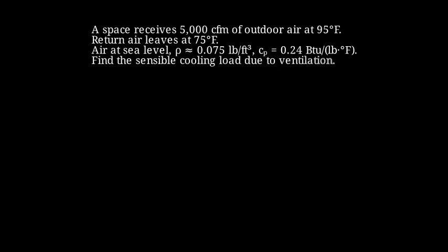Let's calculate the sensible cooling load due to ventilation. A space receives 5,000 cubic feet per minute of outdoor air at 95 degrees Fahrenheit. The return air leaves at 75 degrees Fahrenheit. All air is at sea level, and the density of air is approximately 0.075 pounds per cubic foot, and the specific heat at constant pressure is 0.24 BTU per pound degree Fahrenheit. What is the sensible cooling load attributable to ventilation?